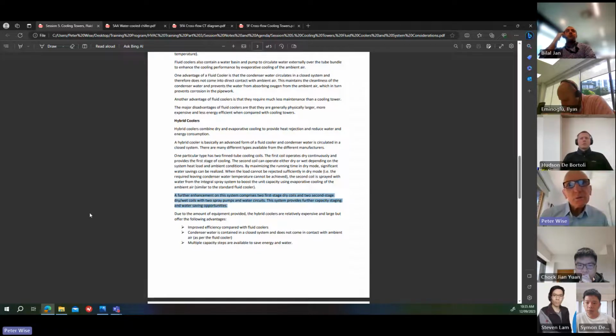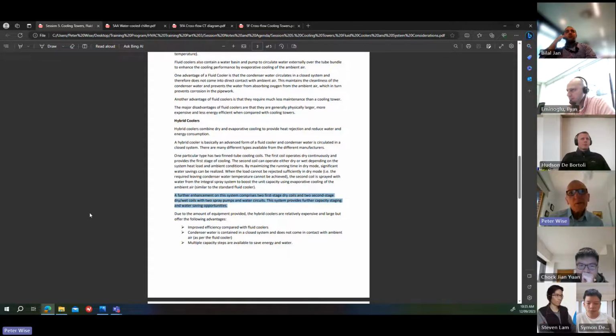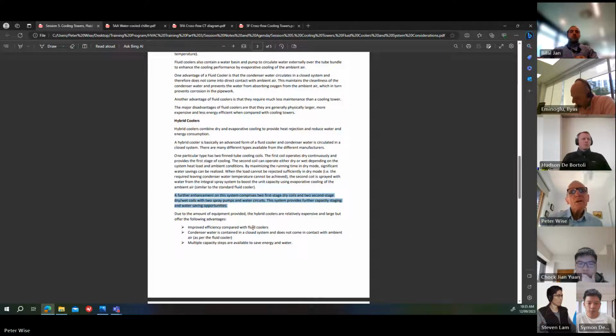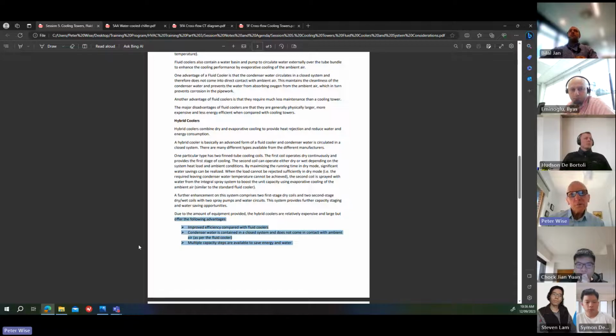The further enhancement on the system I just described comprises two first-stage dry coils and two second-stage dry or wet coils with two spray pumps and water circuits. So lots of bits and pieces, but greater energy efficiency. It provides further capacity staging and water saving opportunities, and potentially greater efficiency than a fluid cooler. Due to the amount of equipment provided, the hybrid coolers are relatively expensive and large, but they have the following advantages. They have improved energy efficiency compared with the fluid cooler. Again, condenser water is contained in a closed system. It doesn't come in contact with ambient air, and multiple capacity steps are available to save energy and water.